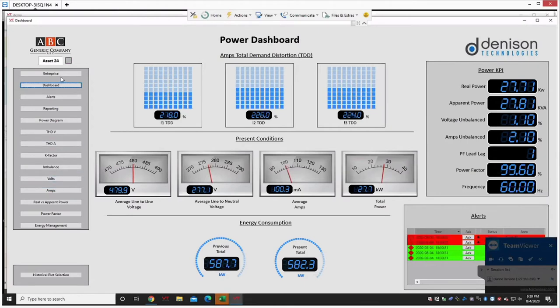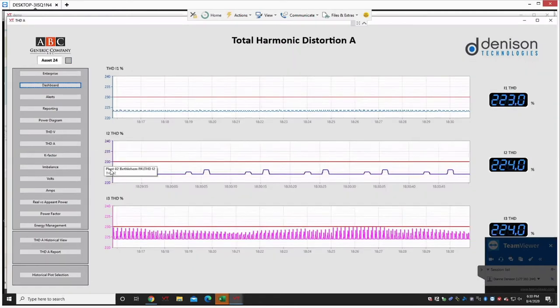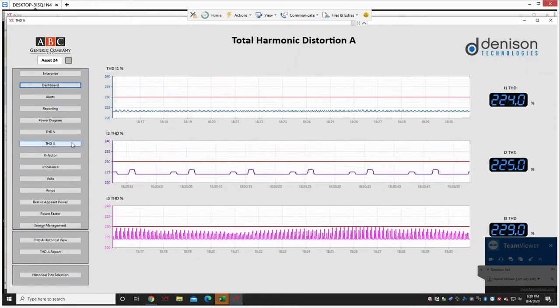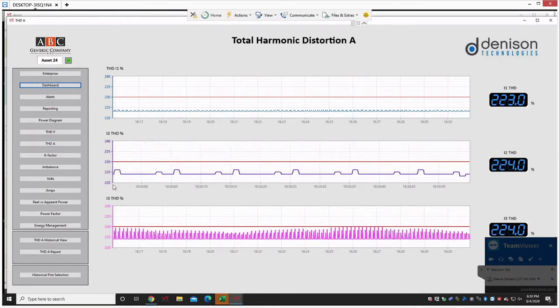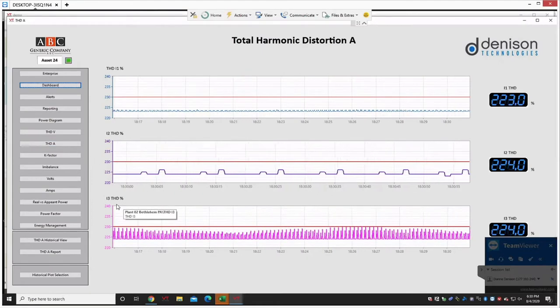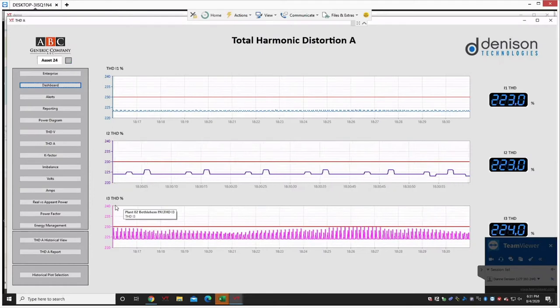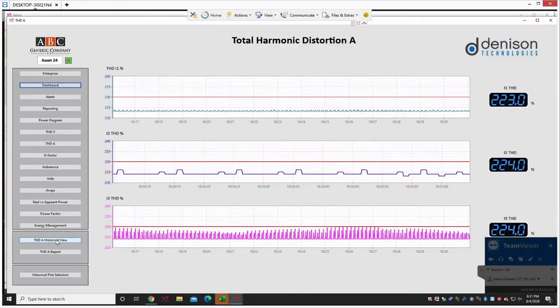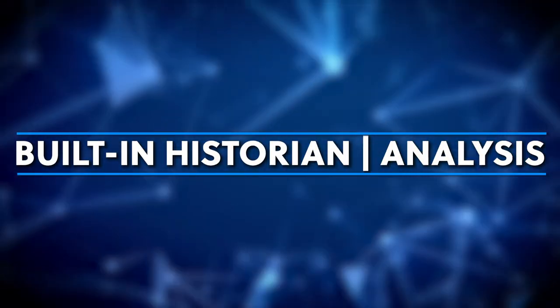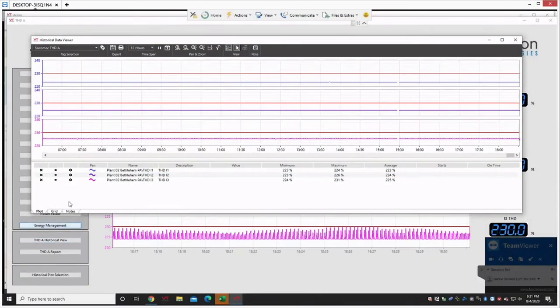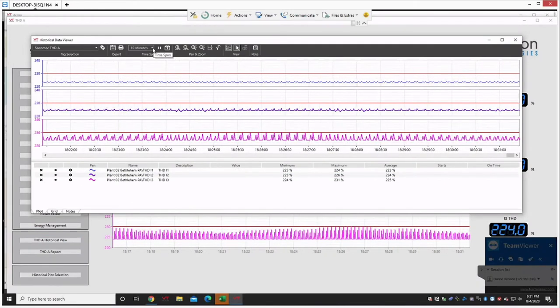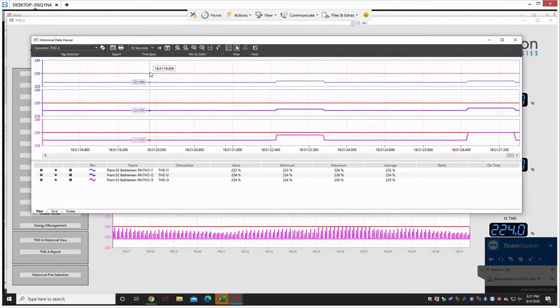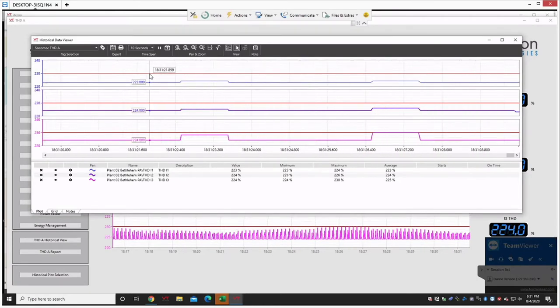For example, we might want to take a closer look into what's now happening with total harmonic distortion. Now we are seeing real-time data pulled every 137 milliseconds, captured and sent to our application reliably for analysis. We are now showing total harmonic distortion and I3 levels beyond tolerance, requiring further review. Data can be logged and stored for up to 5 years using a built-in historian. Changing the horizontal scale from 10 minutes to 10 seconds, we now see gradation down to the millisecond level.